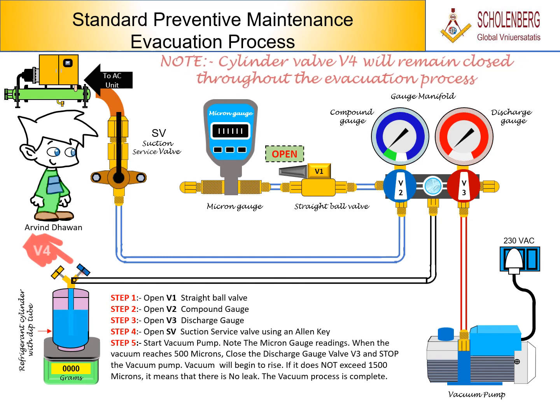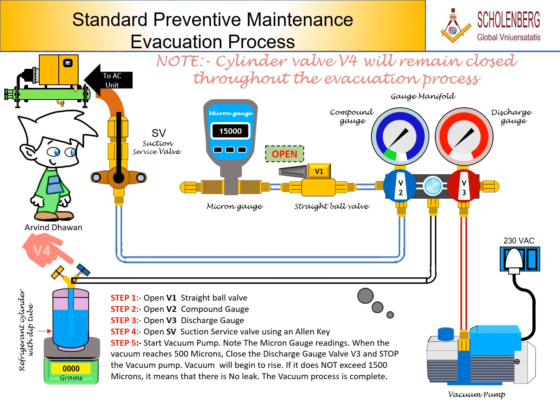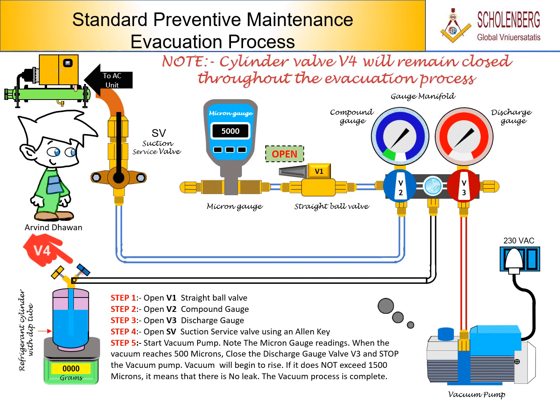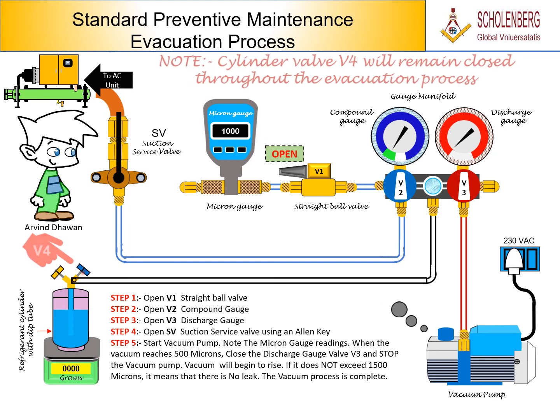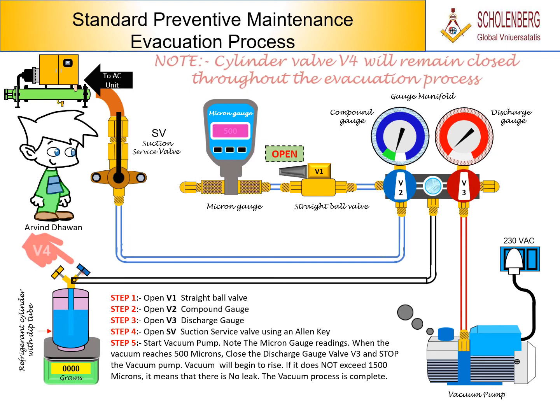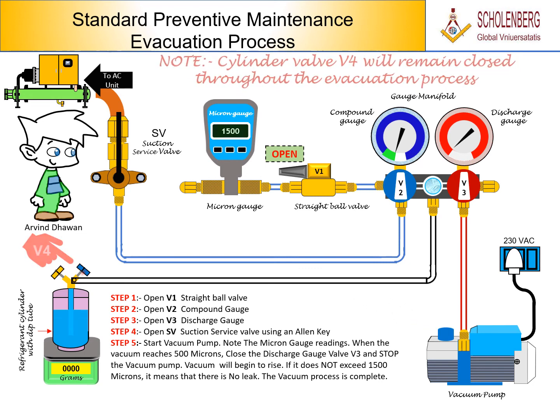Step 5. Start vacuum pump. Note the micron gauge readings. When the vacuum reaches 500 microns, close the discharge gauge valve V3, and stop the vacuum pump. Vacuum will begin to rise. If it does not exceed 1500 microns, it means that there is no leak. The vacuum process is complete. Step 6. Close straight ball valve V1.